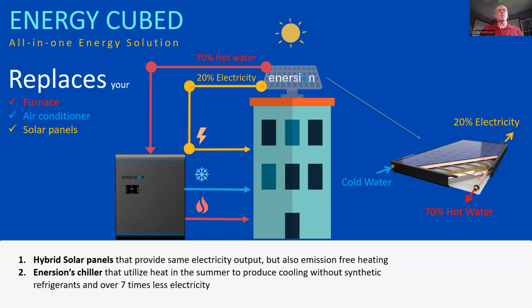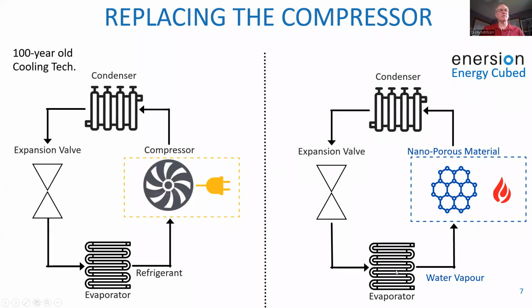The refrigerant water is presumably distilled and in a closed loop — are there other, more efficient refrigerants that could be used, or are you deliberately using water despite technical limitations? Water is amazing because its latent heat is 2200 kilojoules per kilogram — it's a great refrigerant. It's bad because you need to keep a low pressure, but we've mastered low pressure well over the last 6 years, so we know how to keep the system at low pressure quite well. Water works nicely for us, and it's cheap, and since it's a closed loop we're not consuming it at all. We could potentially use other solvents — we've tested other refrigerants and could go to freezing temperatures if needed, but that's not in the commercialization pathway right now.